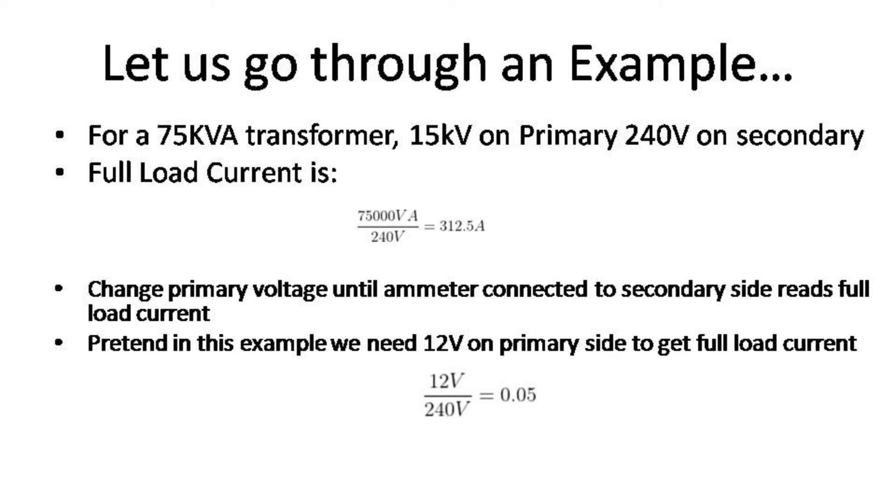Now first of all, let's find out our full load current. Our full load current can simply be 75 kVA divided by 240, which equals 312.5 amps.